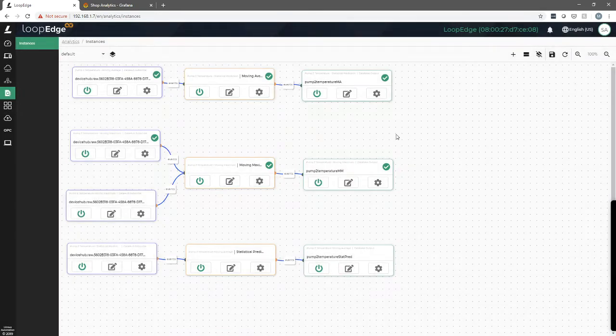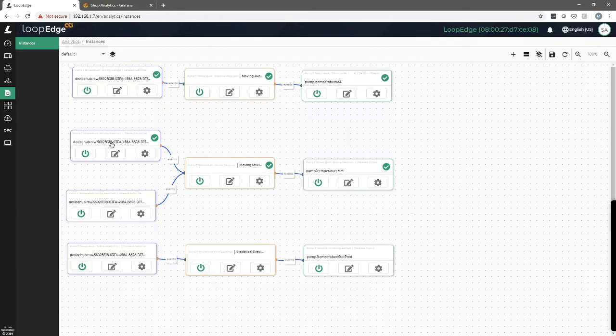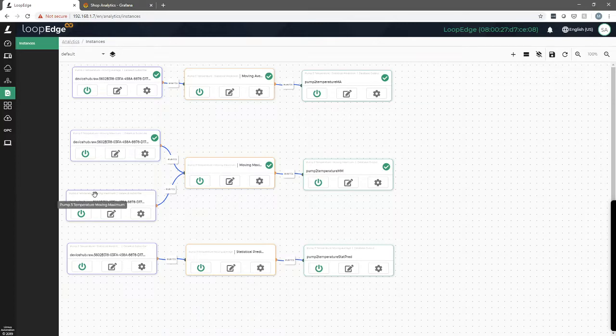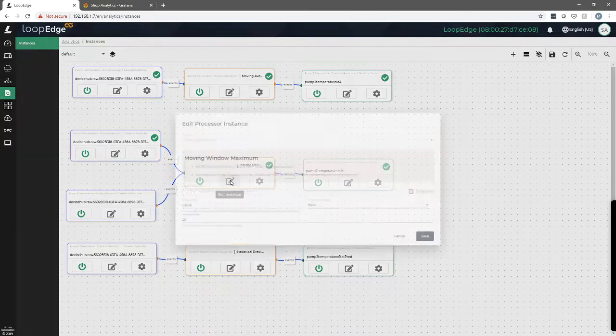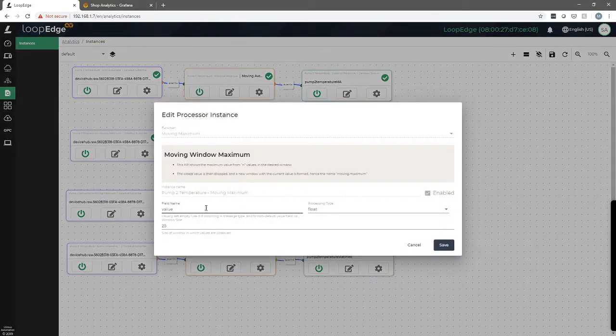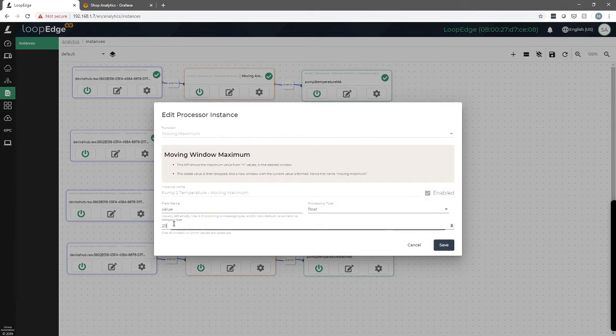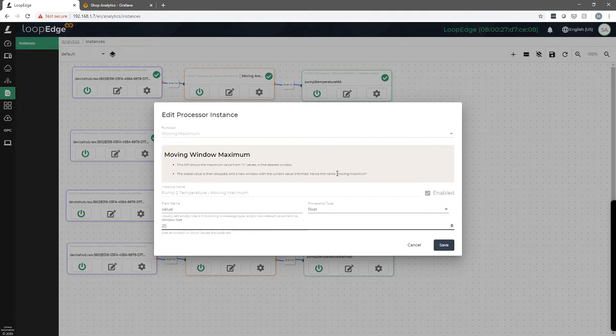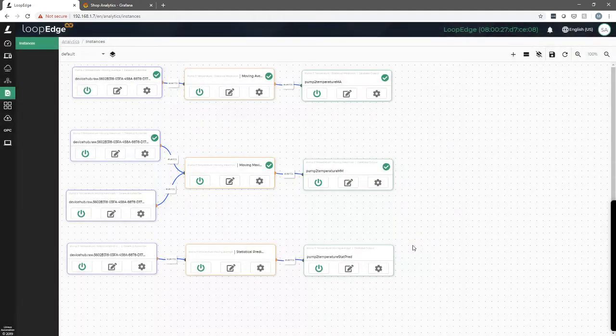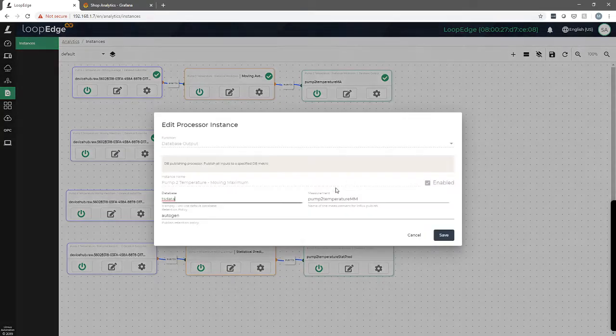So if you look at the second and third flows that we have here, same thing. Here we have two inputs coming in. One is the pump two temperature, one is the pump three temperature. And we're doing a moving maximum. So same idea, 25 is the window size. So the last 25 values will be the calculation window. But this time it's going to do a maximum. So it's going to pump out the maximum value it's seeing over the last 25. And again we're writing this to a database TS data and this we're calling pump two temperature mm.